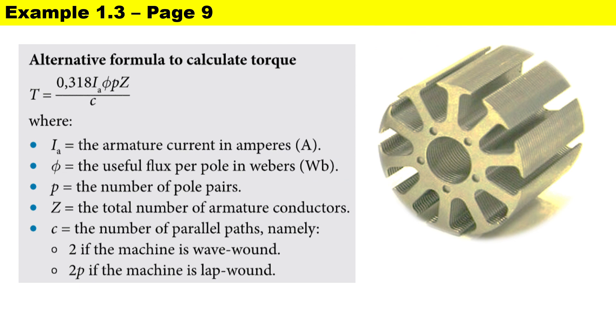In the formula, Ia is the armature current measured in amperes, the flux per pole measured in weber. Small letter p is the number of pole pairs, z is the total number of armature conductors, and c is the number of parallel paths. If it's wave wound, c is equal to two, and if it's lap wound, c is equal to two times small letter p.